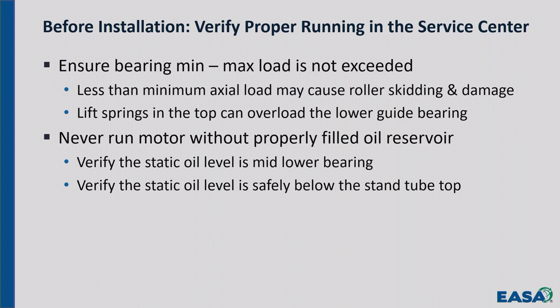You can't take those measurements when the machine is assembled. You would have to take those measurements when it's disassembled. Where's the top of the stand tube compared to the lowest ball in the bearing, when it's not running? Okay, so verify that.